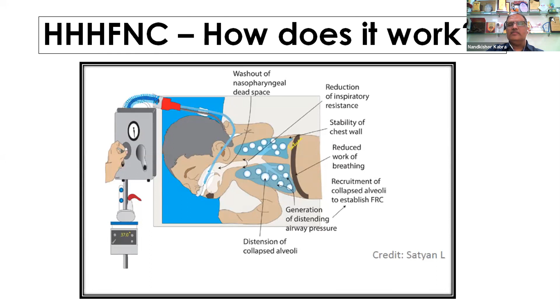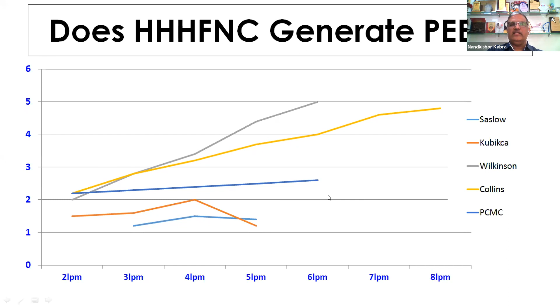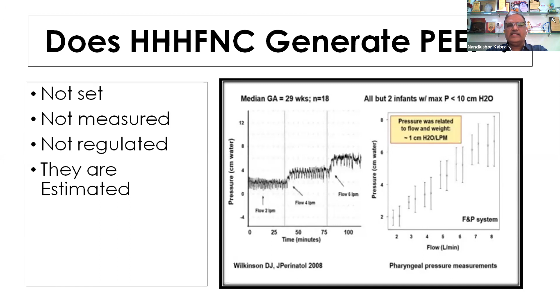Now the question is, does high flow generate PEEP? And the answer is yes. The only thing is that you don't know consistently at what liters how much pressure will be generated, because the results from various studies, when you plot them on a graph, look very different. And what you would usually find is that with increasing the flow, there is increase in the pressure. Generally, suppose the flow is 4 liters, roughly you can subtract 1 from that, and that would be the pressure roughly generated, but there can be lots of variation. So the problem with high flow is that the PEEP is not set, PEEP is not measured, and PEEP is not regulated, and they are only estimated.